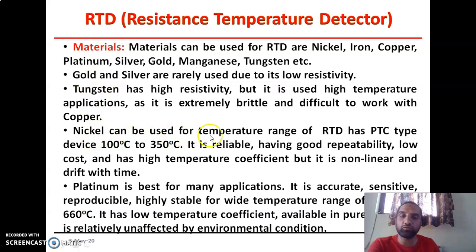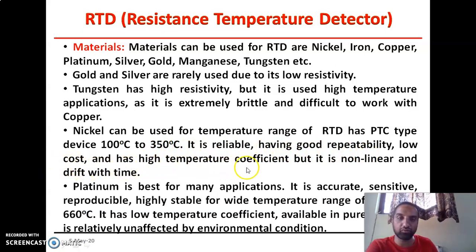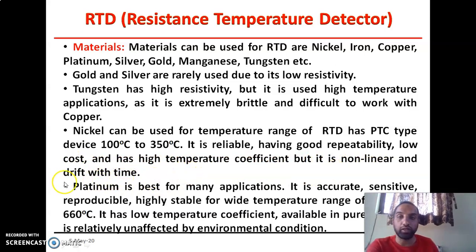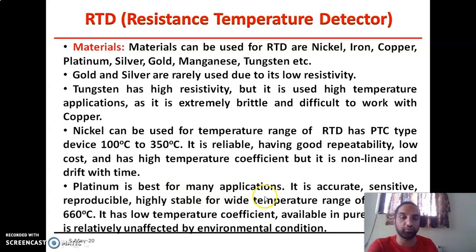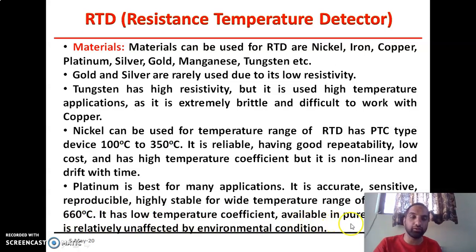Nickel can be used for RTD in the temperature range of −100°C to 350°C. It is reliable, has good repeatability, low cost, and a high temperature coefficient, but it is non-linear and drifts with time. Platinum is the best option for the construction of RTD for many different applications. Platinum is accurate, sensitive, reproducible, and highly stable for a wide temperature range from −190°C to 660°C. It has a low temperature coefficient, is available in pure form, and is relatively unaffected by environmental conditions.